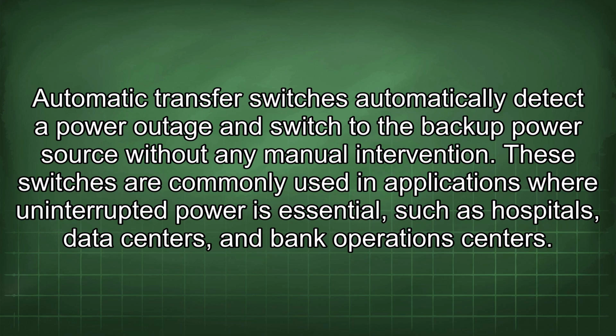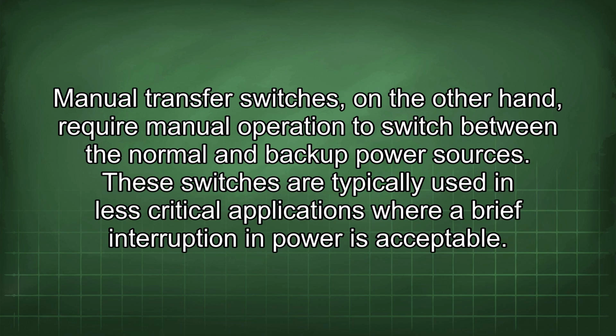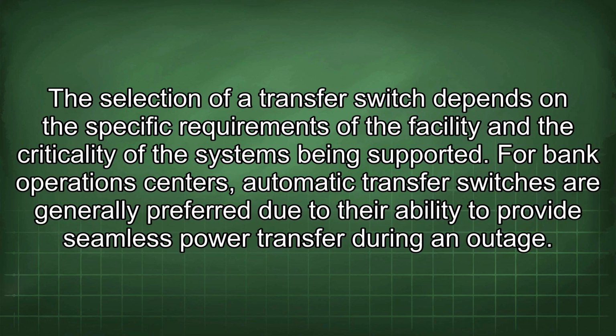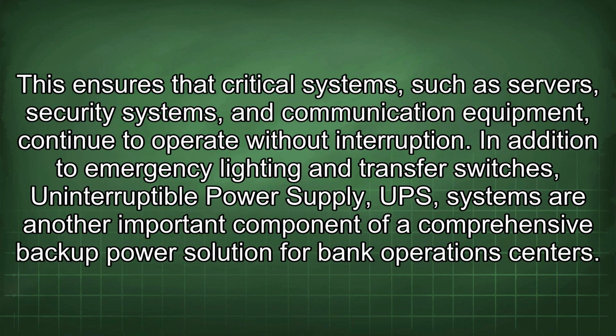These switches are commonly used in applications where uninterrupted power is essential, such as hospitals, data centers, and bank operations centers. Manual transfer switches, on the other hand, require manual operation to switch between the normal and backup power sources. These switches are typically used in less critical applications where a brief interruption in power is acceptable. The selection of a transfer switch depends on the specific requirements of the facility and the criticality of the systems being supported. For bank operations centers, automatic transfer switches are generally preferred due to their ability to provide seamless power transfer during an outage. This ensures that critical systems such as servers, security systems, and communication equipment continue to operate without interruption.